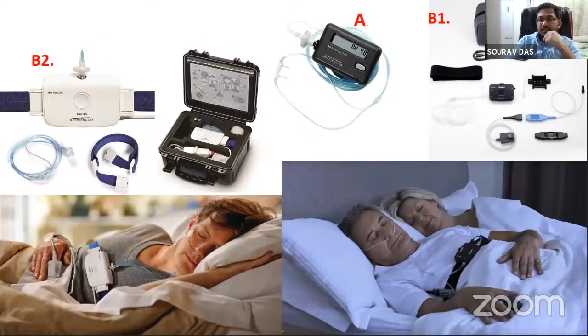If we look here at image A, this is a level 4 device. It measures only the airflow. We can see the nasal cannula here. It measures the airflow of the patient. Sometimes it can also have an associated oximeter, which will measure the patient's desaturation. In other cases, there are devices which measure only the oxygen saturation or desaturation of the patient, and there is no airflow. So basically, this is a level 4 device which measures only one or at most two parameters of that patient.